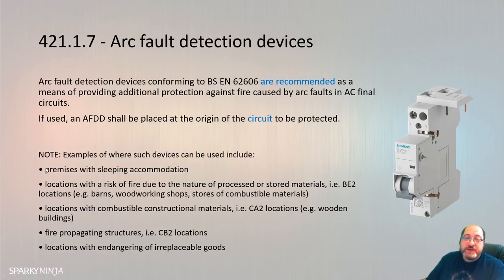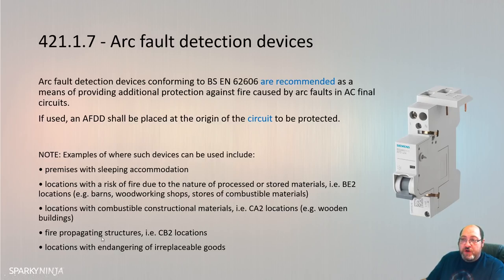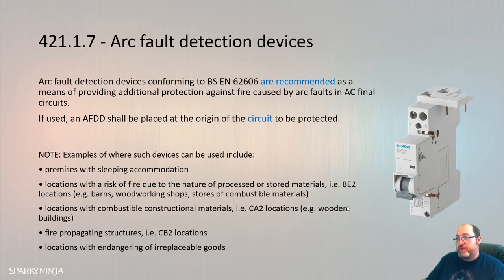How you decide on AFDDs is down to a risk assessment. Examples of where such devices can be used include premises with sleeping accommodation, locations with a risk of fire due to the nature of processes or stored material, locations with combustible constructional material or fire-propagating structures, and locations where irreplaceable goods are stored. Wherever there's a large financial or public consequence to fire, or a structure that can help spread fire, these devices would be appropriate.